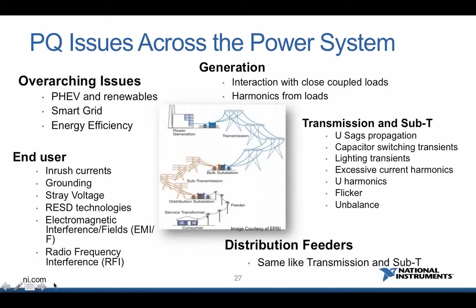If you look at that slide, it mentions some issues connected with customers suffering from bad quality of electrical energy. And it can be very significant if, for instance, the customer is running some kind of technology which is very sensitive to bad quality of electricity. And there is not a single generic solution to solve the power quality problem. An optimum solution needs to be designed for each site, taking into account the above mentioned factors. So to be able to determine the source of the bad power quality, we have to have measuring instruments which give us a clear picture of where the source of the bad quality of the electricity is, and then find the appropriate measure which will improve or remove the situation causing the bad power quality.